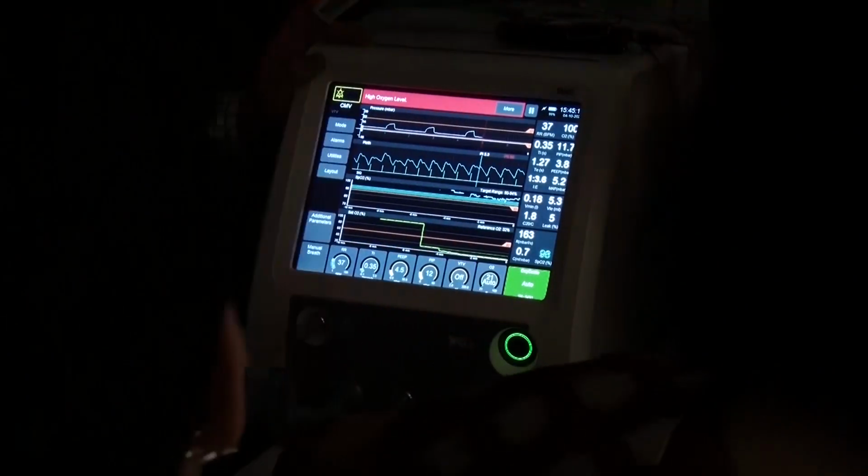All the things can be seen as your ventilator settings. Let me show you one thing. Here is where you have the FiO2 alarm. You can increase by 40, and here you can go up to 70.